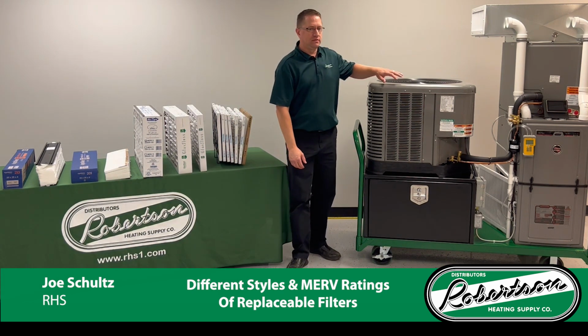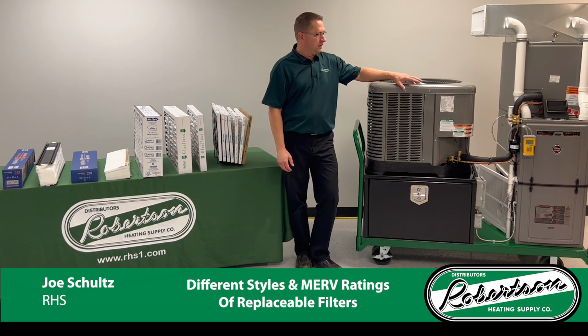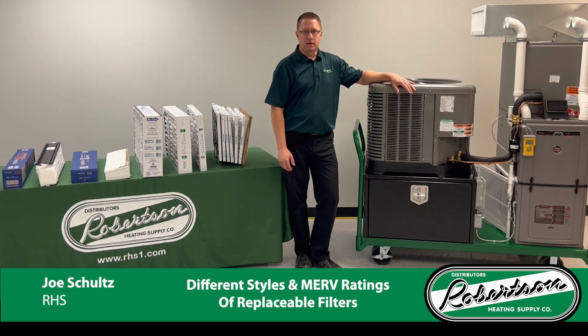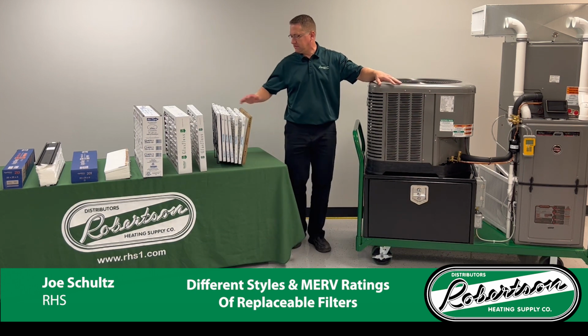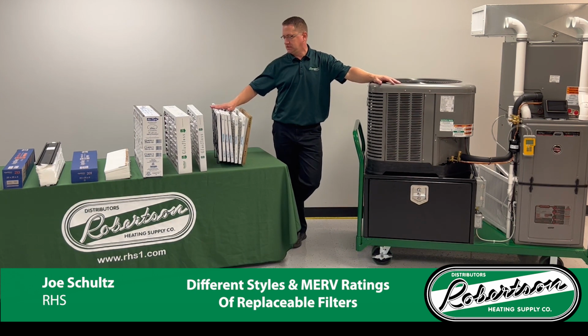So I'd like to move on to our training cart here. I have the system set up so we can test total external static pressure on the system. So I'm going to be using these 14 by 20 by 1 inch filters. They have different Merv ratings on there.